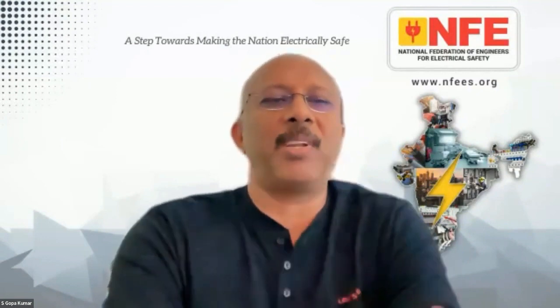But however, to Mr. Paul. So this is an interesting one, because the network providers now, when they are analyzing their network, they actually do a neutral to earth loop impedance test. Now, if you're able to do a neutral and earth loop impedance test, you've got a big problem, because that test shouldn't, in theory, be possible. But on a damaged network, a failed network, you can get a neutral and earth loop impedance.